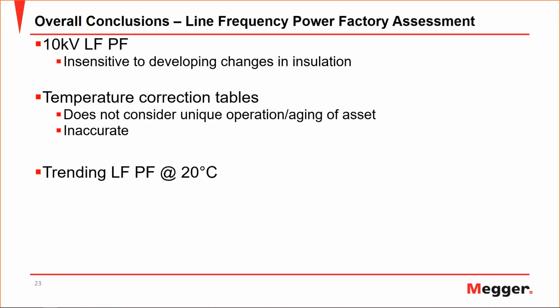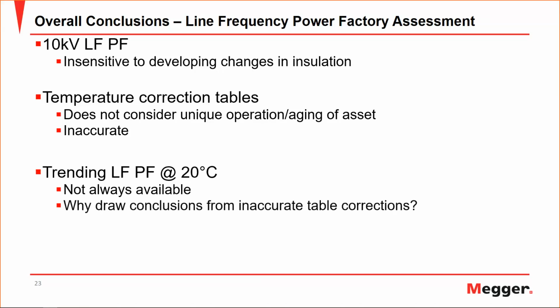The trending of line frequency power factor at 20 degrees C, the results are not always available. It's just not going to be something that will be readily available all of the time, and these 20 degrees C values are calculated using inaccurate temperature correction tables. So my question for everybody would be, why would you want to continue to evaluate and compare historical results that were corrected in an inaccurate way? It just does not give you the best information possible.